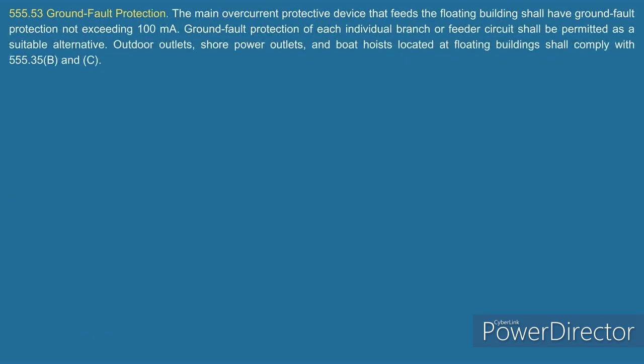And then it talks about ground fault protection. It says the main overcurrent device that feeds the floating building shall have ground fault protection not exceeding 100 milliamps. Ground fault protection for each individual branch or feeder circuit shall be permitted as a suitable alternative. And then it says outdoor outlets, shore power outlets, and boat hoists located at floating buildings shall, look here, comply with what? Where we started, 555.35(B) through (C), which says they're what?